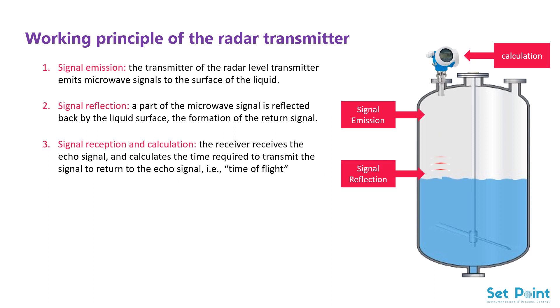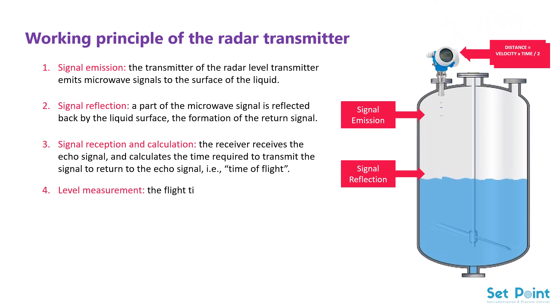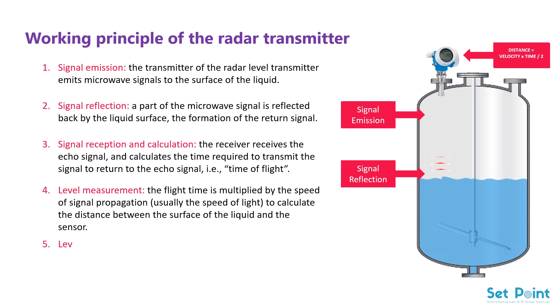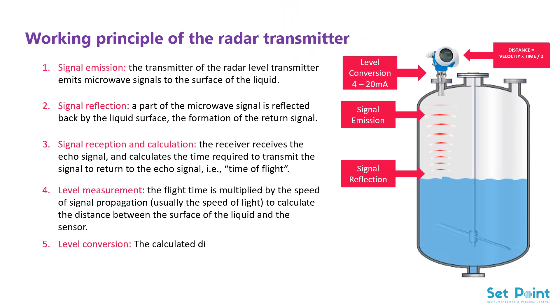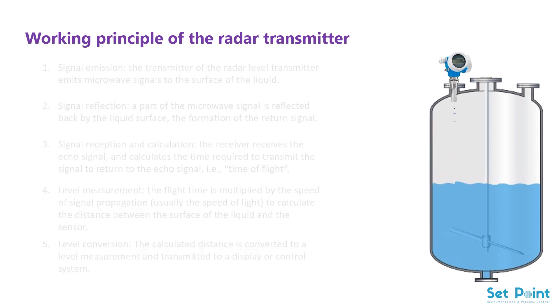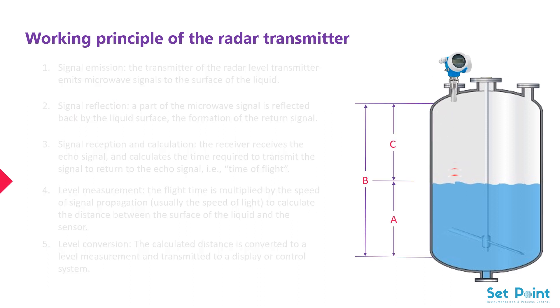Time of flight. Level measurement: the flight time is multiplied by the speed of signal propagation, usually the speed of light, to calculate the distance between the surface of the liquid and the sensor. Level conversion: the calculated distance is converted to a level measurement and transmitted to a display or control system. Here we can see that the time of flight is used to calculate the distance.